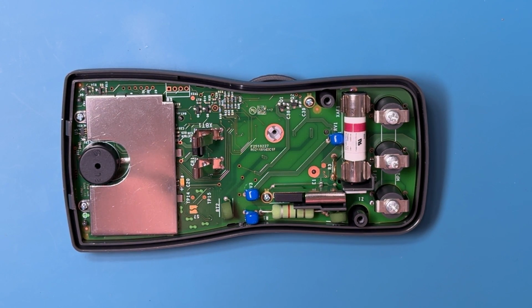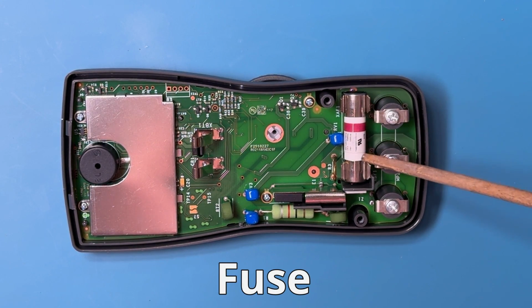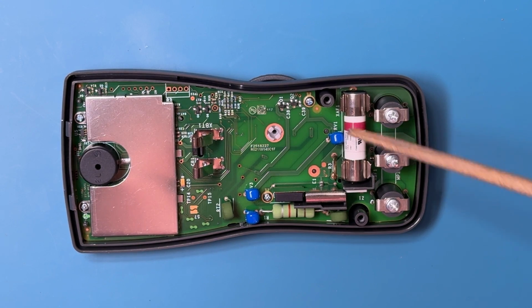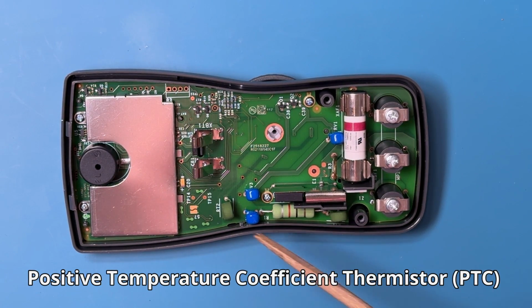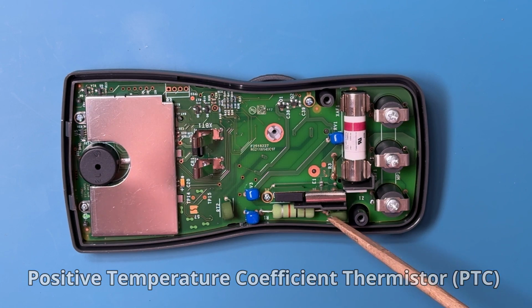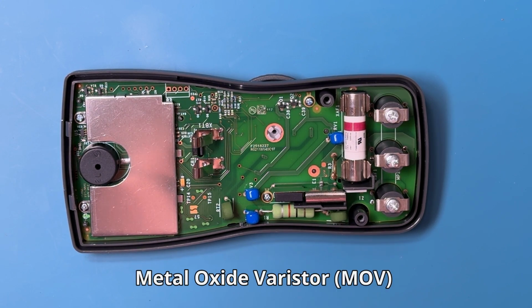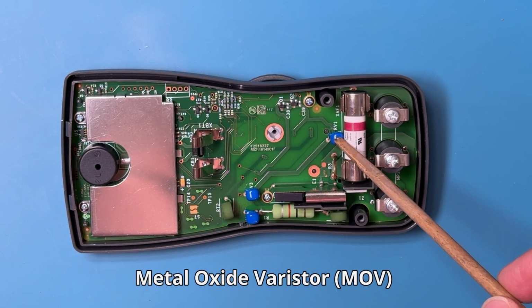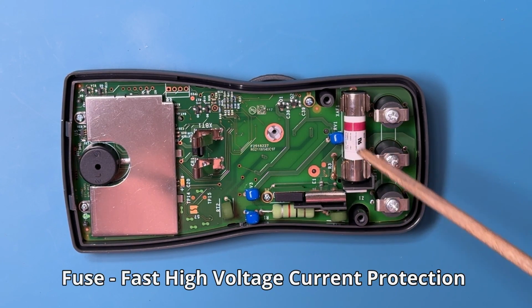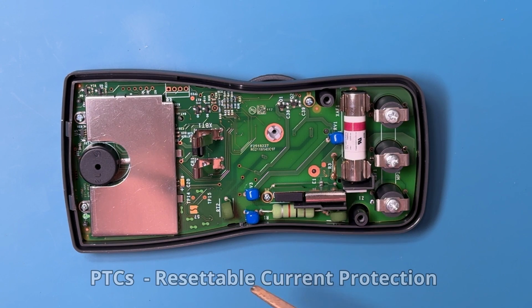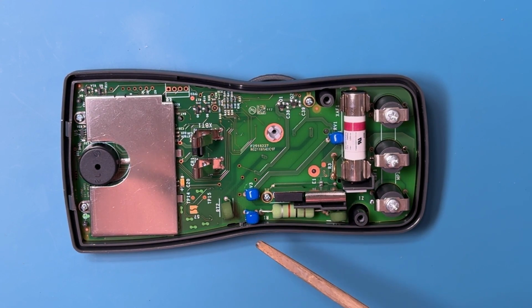Protection mechanisms within multimeters come in many forms. There are electrical safety components like fuses, positive temperature coefficient thermistors, or PTCs, down here, and metal oxide varistors like MOVs, here. Fuses will blow if current goes too high and can handle high voltages. PTCs are considered resettable fuses and will inhibit electrical flow if current goes too high. However, they are usually limited to about 60 volts.